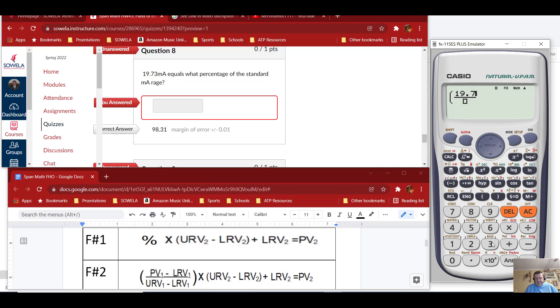Number 8: 19.73 milliamps equals what percentage of the standard milliamp range? Looking for a percentage and not given one, so I use formula two. Open parentheses, over-under: 19.73 minus the lower range value of 4, over 20 minus 4. Close parentheses, times, open parentheses — for percentage: 100 minus 0, plus 0. Equals 98.31. Almost 100% — I can tell just by how high the milliamp value is.